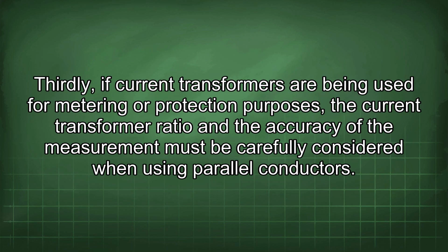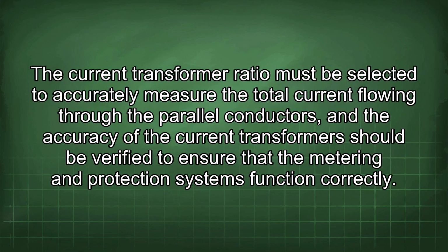Thirdly, if current transformers are being used for metering or protection purposes, the current transformer ratio and the accuracy of the measurement must be carefully considered when using parallel conductors. The current transformer ratio must be selected to accurately measure the total current flowing through the parallel conductors, and the accuracy of the current transformer should be verified to ensure that the metering and protection systems function correctly.